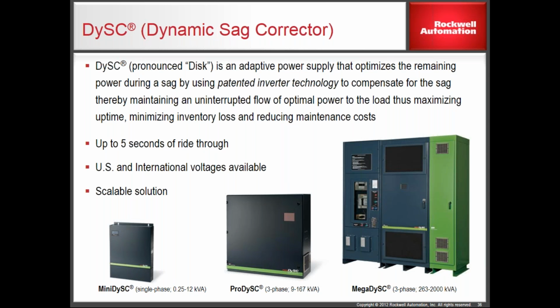The other thing this does for me is it gives me energy in the case of a true outage. So for most of us, once a year we may have an outage. And when that occurs, we can't steal current from nothing. What we have is our capacitive energy left. And as long as we have at least 1/10 of a second at running load, then we're going to protect your equipment from damage. Because in a real outage, imagine a real outage now. Somebody hit a pole, they're going to take you down, the lines hit the ground, they short, they bounce, they short again. Maybe on the 3rd try something breaks and they cross.